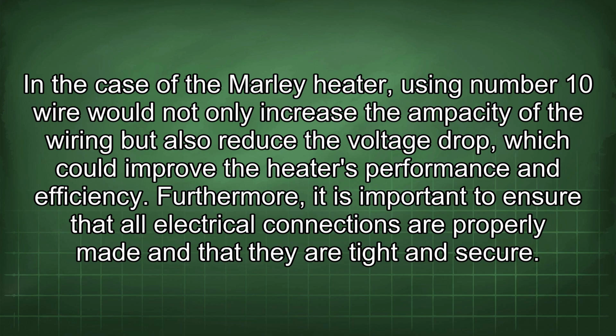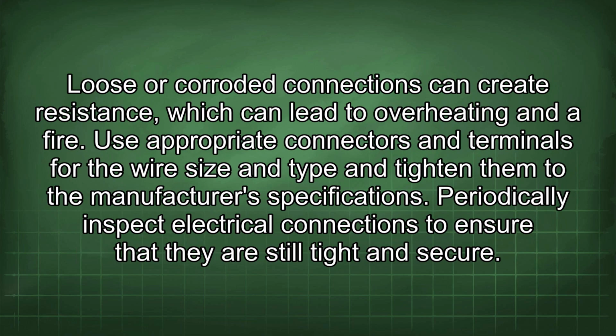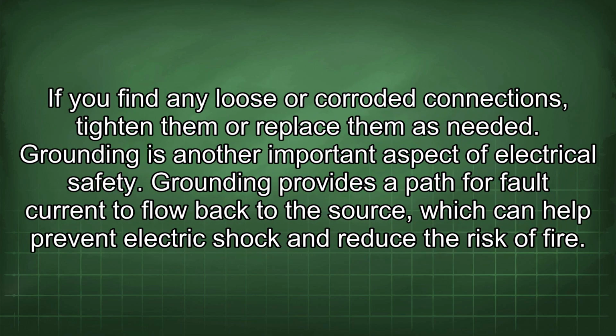Furthermore, it is important to ensure that all electrical connections are properly made and that they are tight and secure. Loose or corroded connections can create resistance, which can lead to overheating and a fire. Use appropriate connectors and terminals for the wire size and type and tighten them to the manufacturer's specifications. Periodically inspect electrical connections to ensure that they are still tight and secure. If you find any loose or corroded connections, tighten them or replace them as needed.